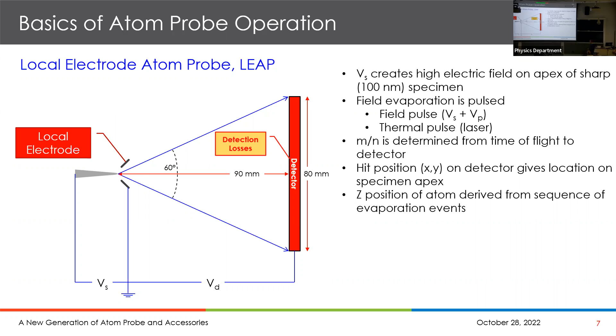One thing to know is that today's detector technology gives us about 80% of the atoms. It's based on microchannel plates being the first line of detection, and they only get about 80% of the atoms. That's something I'm going to address, because what we would like to have in these images is 100% of the atoms. But for all the beauty of that kind of image, there are some detractions, and this is the most serious one: in the atom probe, we don't have a high spatial fidelity in general.